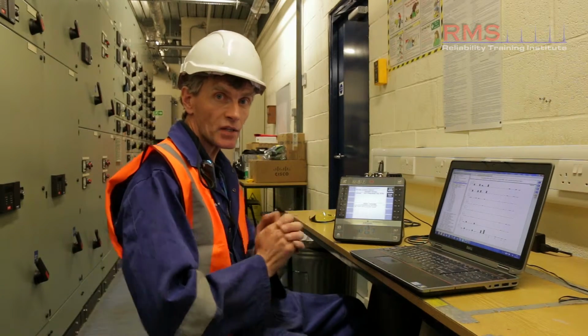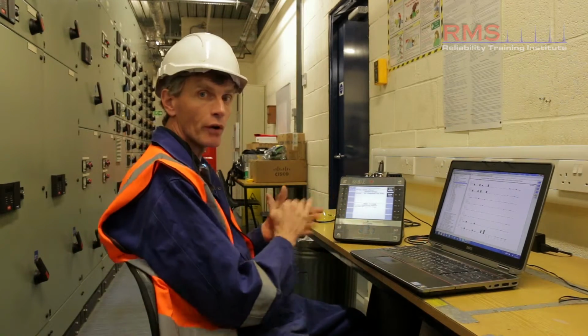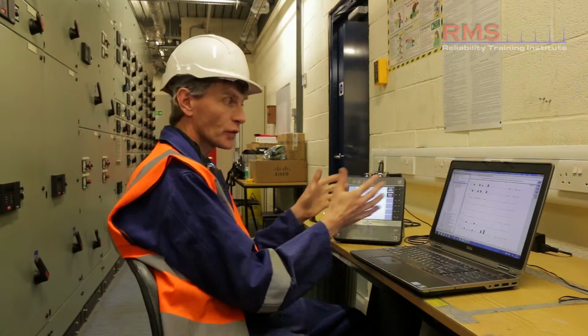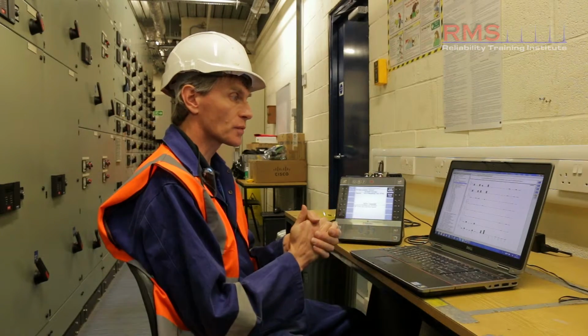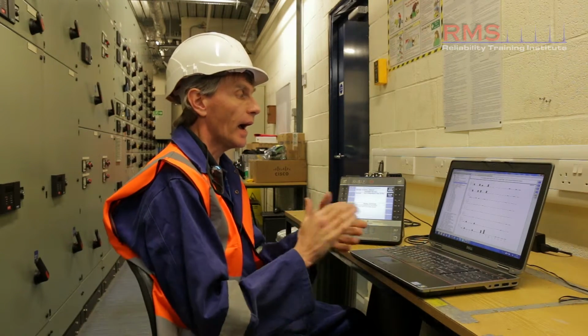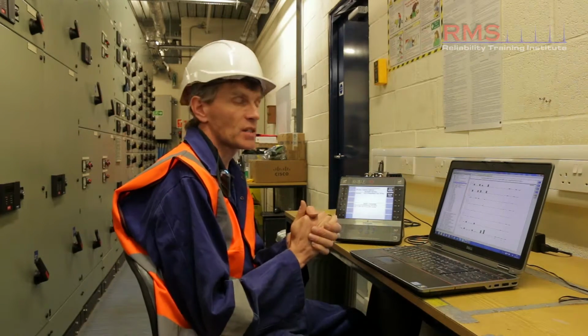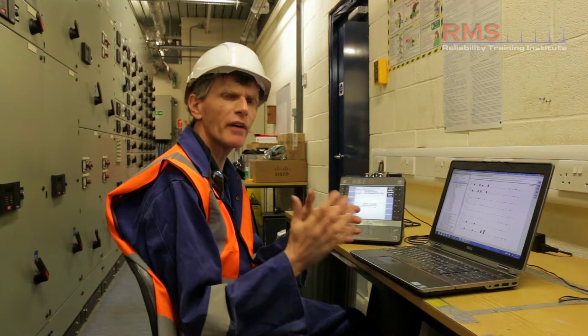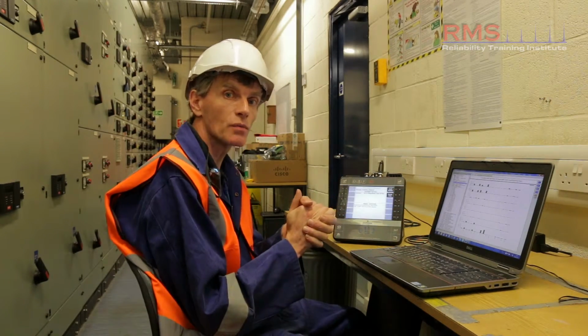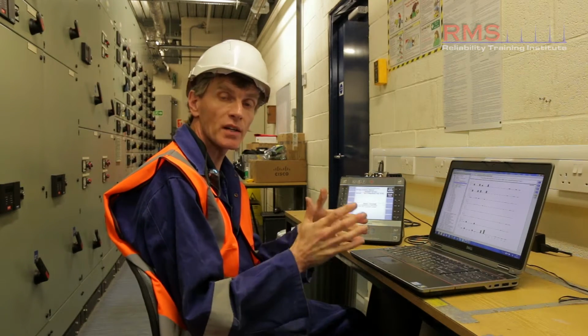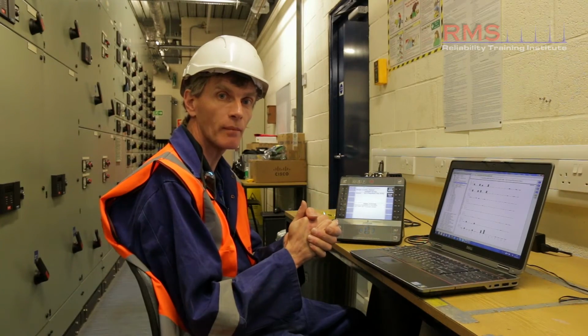Okay, so I guess that short introduction has given us an overview of data collection and how we've secured the data on the vibration computer system. We've shown how the data was secured on there, and we've run an exception report, a very basic way to look for abnormalities and changes that may have occurred. And we've shown a basic overview of some of the plots that we can look at to assess in a very basic way the general situation with a particular machine. The one we looked at was healthy, everything was green and good, and the trends were stable, so nothing to be concerned about in that particular case. So I hope that's been of some help and some value.